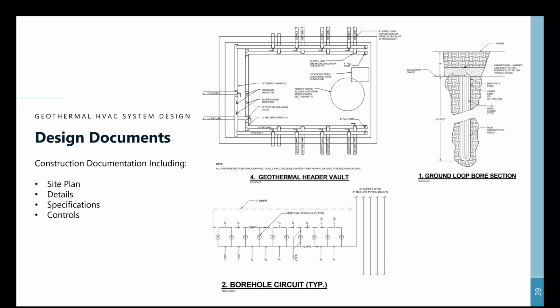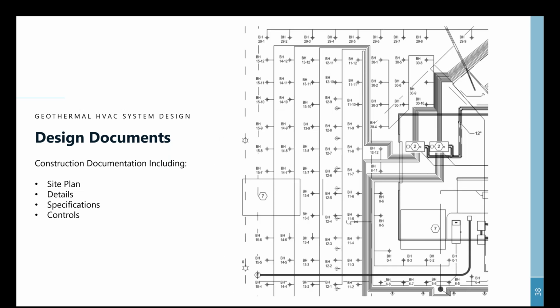In addition to the plan, there's a lot of detail on how to construct these systems—ground loop bore sections showing specifically for your project how the geothermal borehole is constructed, the depth, the type of grout used, and the general arrangement. There's also a geothermal header vaults detail; going back one slide, keynote 2 calls out where the headers are in the geothermal bore field.